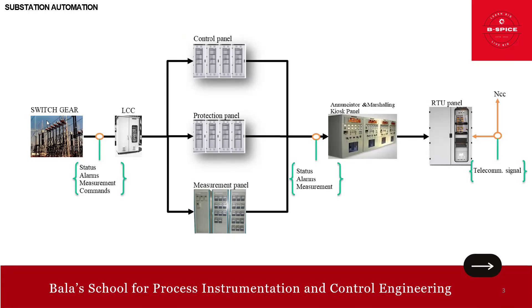Control means switchgear manages the flow of electrical power by switching circuits on and off. Protection means it protects the electrical system from faults by interrupting the flow of electricity during abnormal conditions such as short circuits or overloads. Isolation means it isolates a section of the electrical network for maintenance or in case of fault, ensuring safety for personnel and equipment. The components include circuit breakers, disconnect switches, fuses, and protective relays.